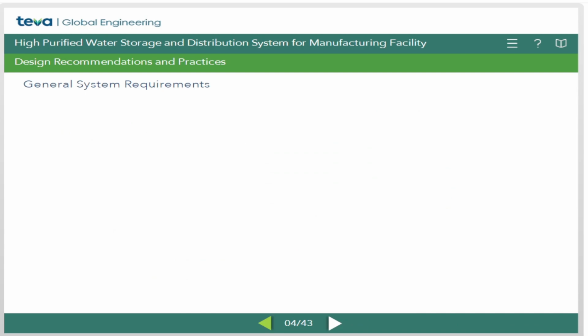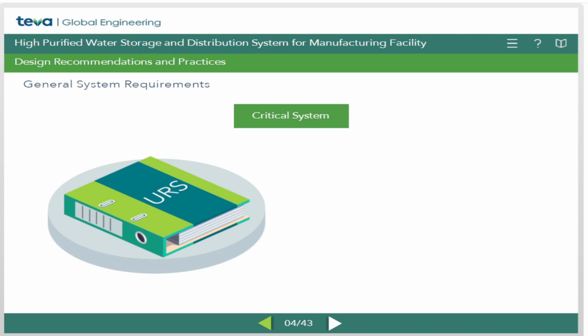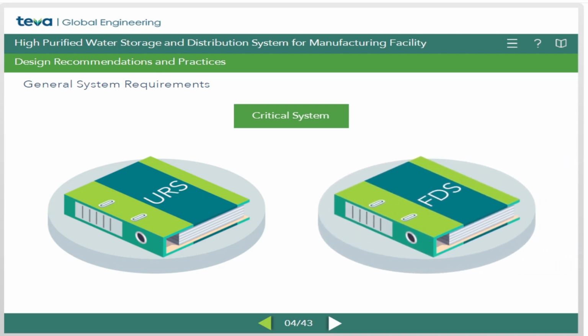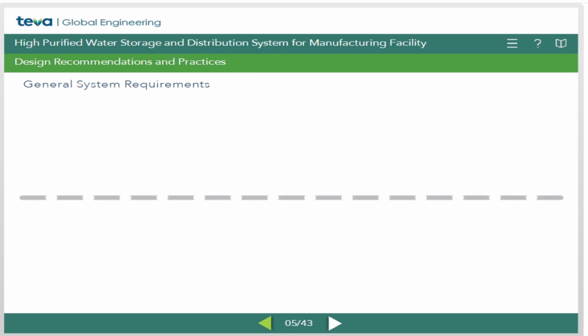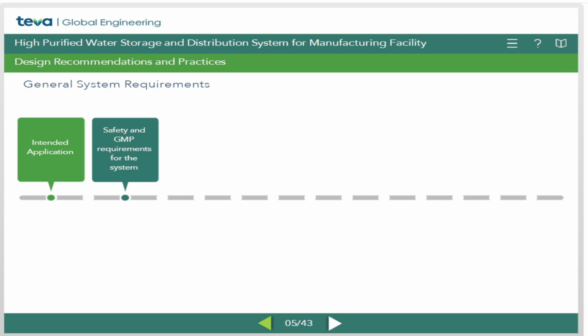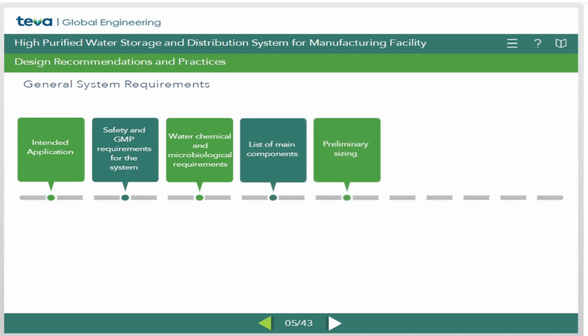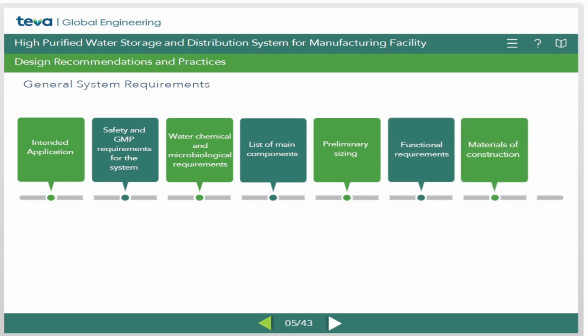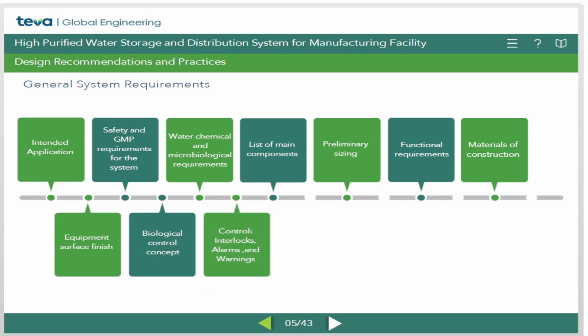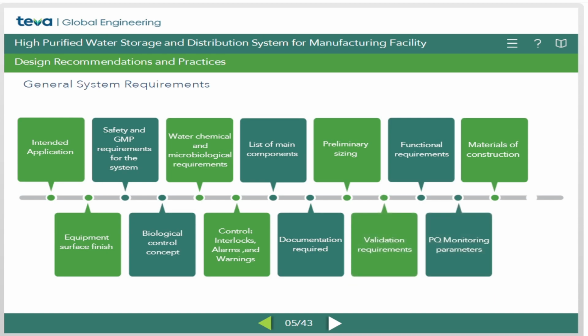The purified water storage and distribution system is considered as a critical system. Hence, a well-defined user requirements specification and a functional design specification document must be prepared. The URS document must specify intended applications, safety and GMP requirements for the system, water, chemical, and microbiological requirements, list of main components, preliminary sizing, functional requirements, materials of construction, equipment surface finish, biological control concept, control interlocks, alarms, and warnings, documentation required, validation requirements, performance qualification monitoring parameters, and consumer flow rates and temperatures.